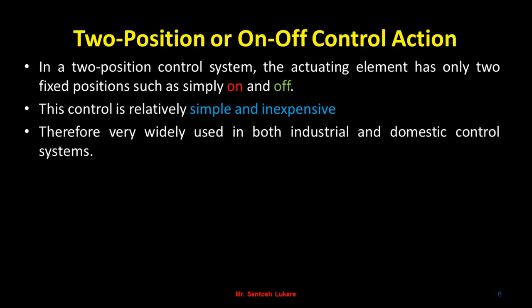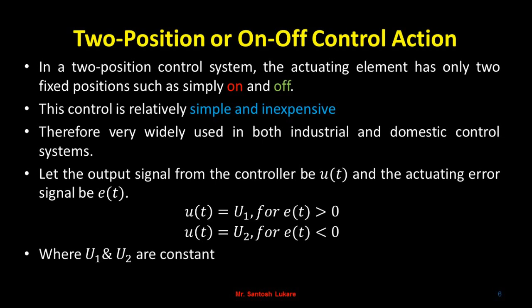The output of this controller, you can call it u(t), is generated depending upon the error signal which is given to the controller. Mathematically one can write u(t) is equal to U1 for the error signal e(t) greater than 0, or u(t) is equal to U2 for the error e(t) less than 0. In most cases, U1 and U2 are constants, which could be either the 0 value or 1 value, or logically on or off, or sometimes the position of the final control element, which is totally open or totally closed. So U1 is 100% of the output, and U2 is most of the time considered as 0%.